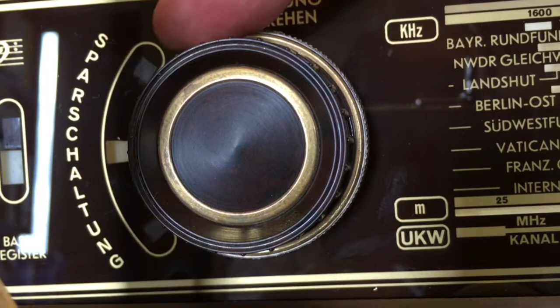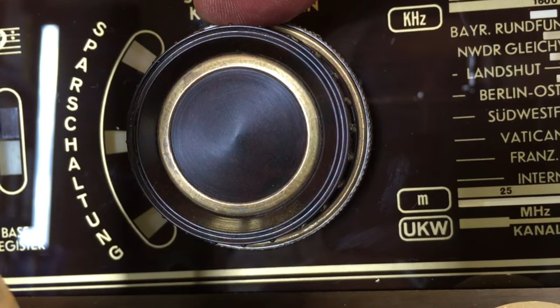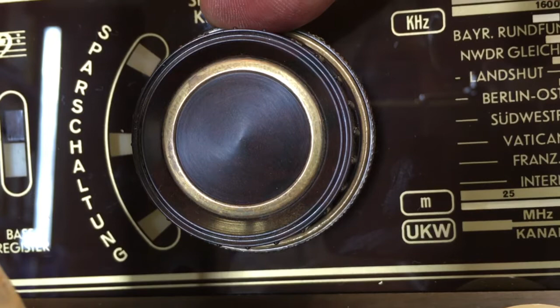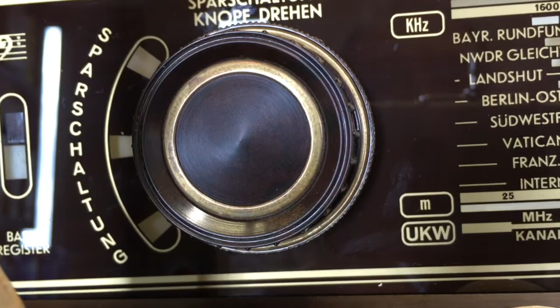I assumed that was a tone function, but obviously it's not. I know it's a switch because when I took the whole front panel out, it's on the back there. It's a toggle switch which is activated and deactivated, a two-way selector, exactly as it shows in the schematic. This thing obviously has the effect of dropping the voltage coming out of the secondary, and we'll check that function when we test the secondary voltage. But it's a new one as well - again, never seen this before.